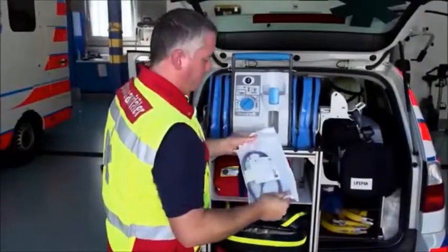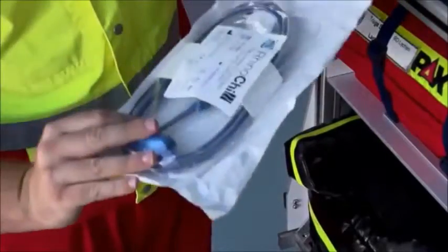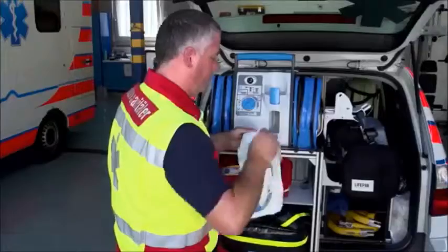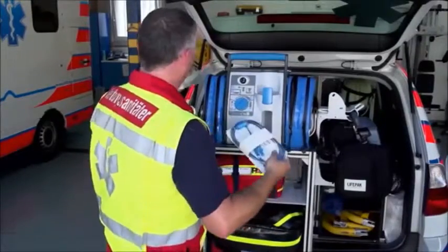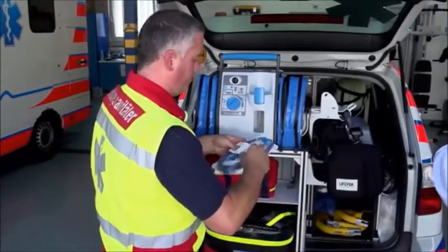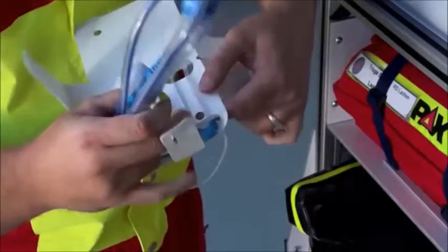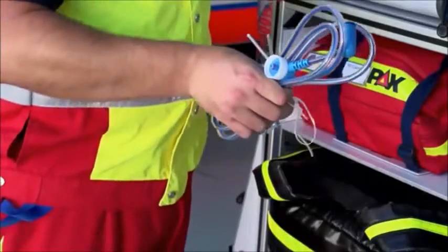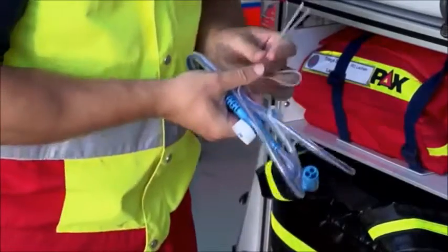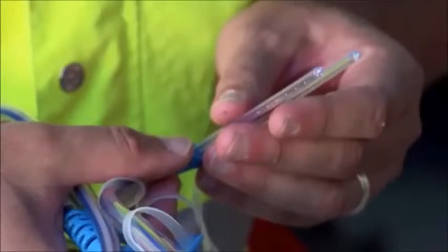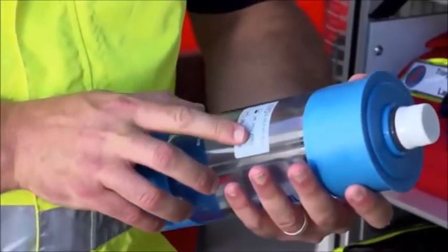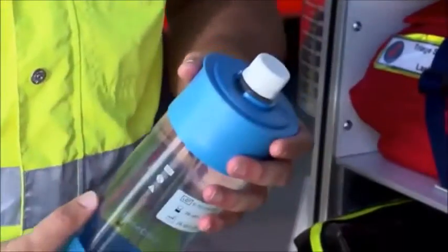Remove the pouch containing the catheter from the box. Inspect the pouch to ensure that it is not damaged. Remove the catheter from the pouch without using any sharp objects to open any of the packaging, and inspect the catheter for cuts, broken connectors, or other abnormalities. Inspect the nasal cannula and ensure that the tips are smooth and round with no burrs, nicks, or cracks. Inspect the coolant bottle for intact end caps and a legible label.